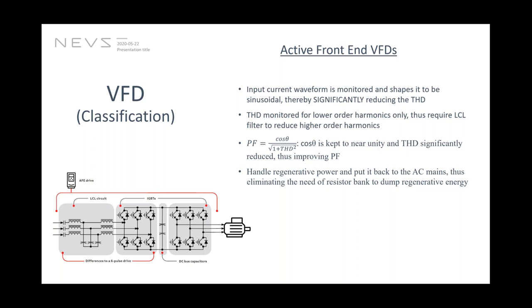And all these, the total harmonic distortion and the good power factor, all this ultimately converts into operational cost, because you don't need any filters for the low frequency harmonics, and a good power factor means that your energy bills, which are in terms of volt ampere, would be lower, and you will save money in the operation as well.